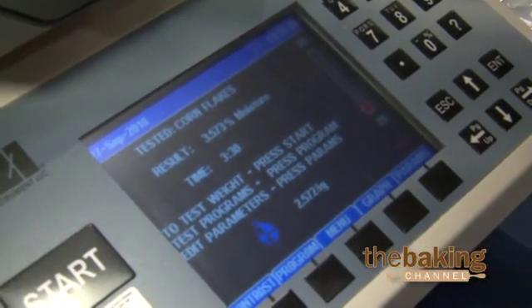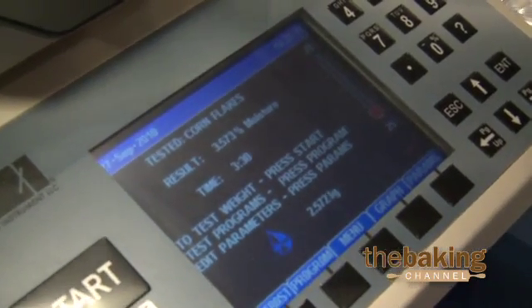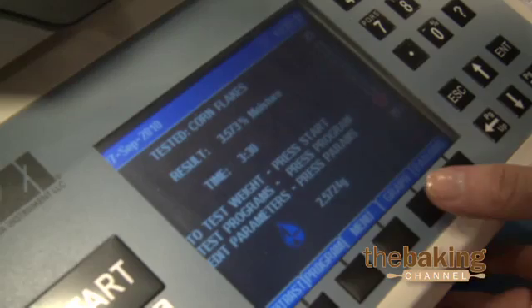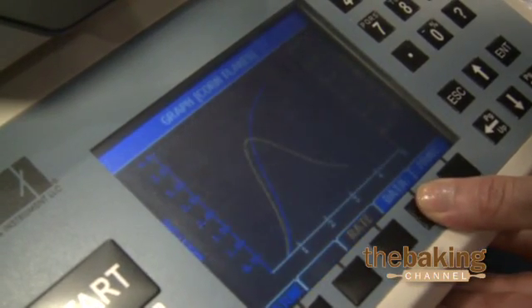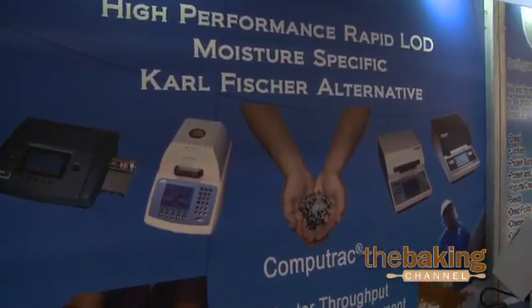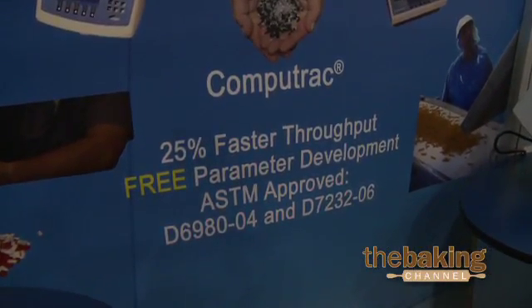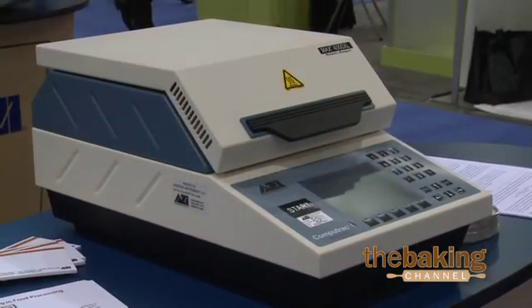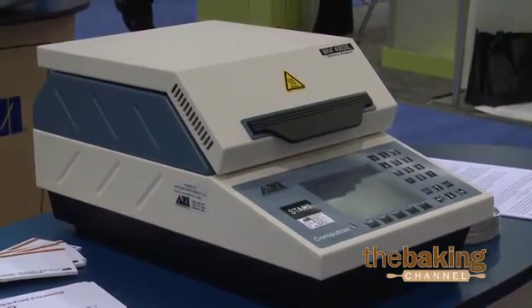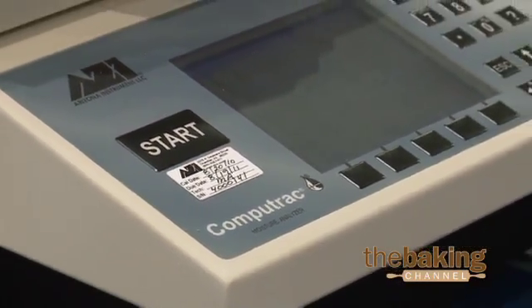Here you can see the results we've achieved when testing cornflakes — the percent moisture that was driven off, as well as the amount of time it took to drive off the sample. You can also view a real-time graphical analysis of the moisture's evolution. We ensure accuracy on our instruments by testing them versus the AOAC standards, whether it be the oven method, vacuum oven, Karl Fischer, or your preferred method of choice. These samples are first tested in our in-house lab on the AOAC method and then tested on the Computrac to ensure accuracy, repeatability, as well as speed of test times.